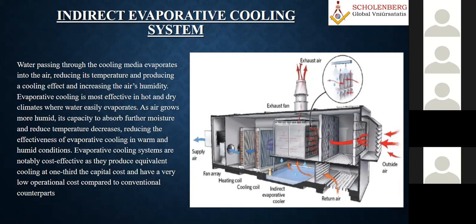Depending upon the project, if you are taking so much outdoor air, why can't you use outdoor air, particularly when you have a dry climate? For example, if you are designing an air conditioning system in a place like Delhi, from February, March, April, May, June, your dry bulb temperature goes almost 45 degrees centigrade, but the humidity is only 20% or 25-30%. If you plot it on your psychrometric chart, you don't even need air conditioning. If you are taking 100% fresh air, instead of taking it at 45 degrees centigrade, you use an air washer to cool it. I know you then have to dehumidify it. That is definitely a disadvantage.